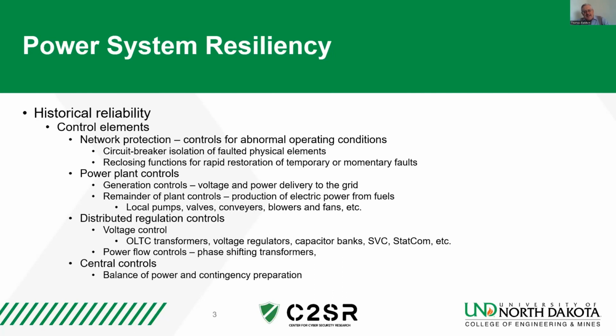Power plants are usually the primary control points for the transmission system. At the distribution level, the distribution substation becomes that control as we break the system up into different areas and provide different levels of control. At the substation, voltage control is important, both with capacitor banks, but important is voltage regulators, and you often find other pieces of equipment there. On-load tap changing transformers, which is very similar but slightly different than voltage regulators, depends on where the voltage problem happens to be and at what level of controllability you want to have it at. Static VAR compensators and STATCOMs are electronic versions of this.